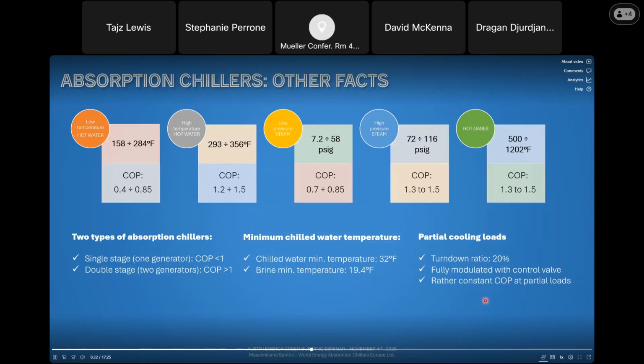Absorption chillers can work in partial cooling loads with a turn-down ratio of 20%. The efficiency at partial load is quite constant, and the cooling demand can be modulated using a control valve for the heat source, unlike compressors that use a variable speed drive inverter. As you can see here, the efficiency of the chiller varies based on the heat source temperature or heat source pressure in case of steam.